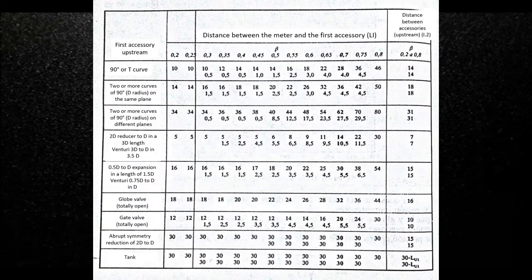Differential pressure elements, on the other hand, require straight pipe runs before and after it. In this table, we can see the general rules where the relation of diameters and distances expressed in pipe diameters are indicated. In general, the section of straight pipe upstream is from 16 to 44 diameters and downstream from 2.5 to 5.